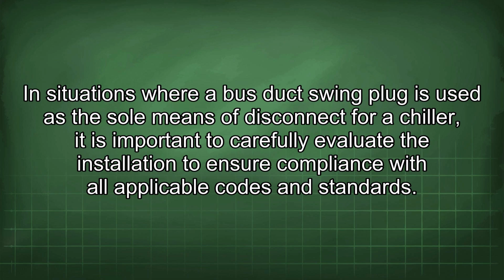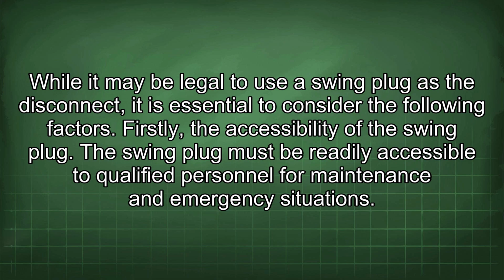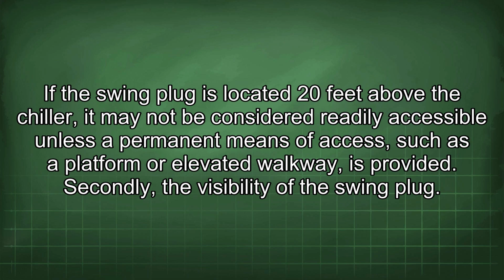In situations where a bus duct swing plug is used as the sole means of disconnect for a chiller, it is important to carefully evaluate the installation to ensure compliance with all applicable codes and standards. While it may be legal to use a swing plug as the disconnect, it is essential to consider the following factors. Firstly, accessibility of the swing plug. The swing plug must be readily accessible to qualified personnel for maintenance and emergency situations. If the swing plug is located 20 feet above the chiller, it may not be considered readily accessible unless a permanent means of access, such as a platform or elevated walkway, is provided.